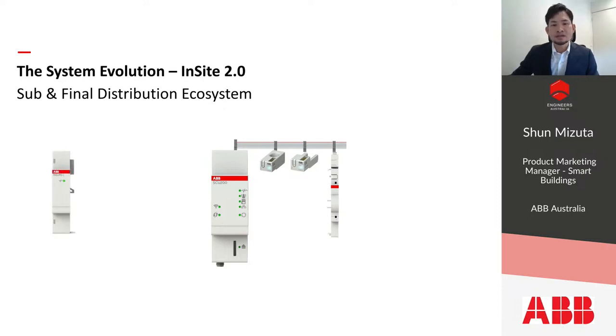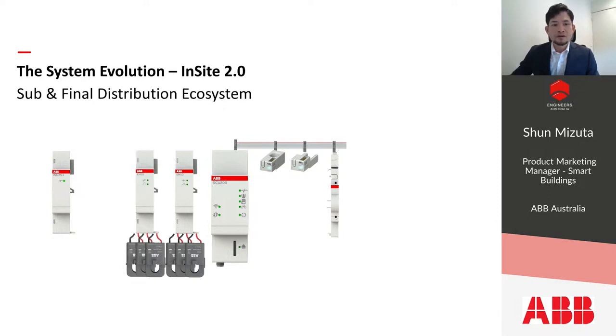If you want to add more functions from the modules, for example, here you need to have a 240 volt power supply to add additional modules, such as energy meter modules like this. And if you want to add multiple of them, that is also possible, up to 5 modules. If you want to add an additional protocol, for example wireless M-bus, we also have a module for that.